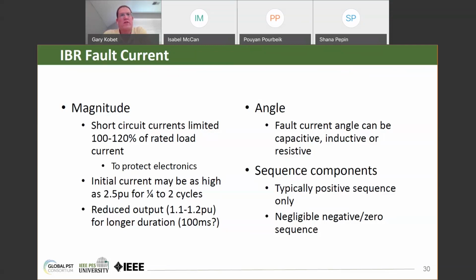And with conventional synchronous machines, that's how protective relays tell the difference. The voltage sags, the current goes up, and the current becomes more lagging. The issue with IBR is the fault current may not respond that way.